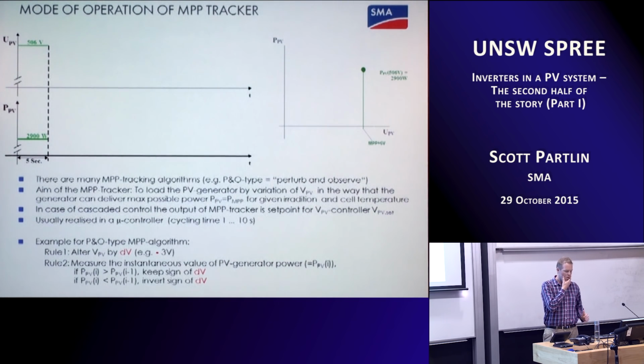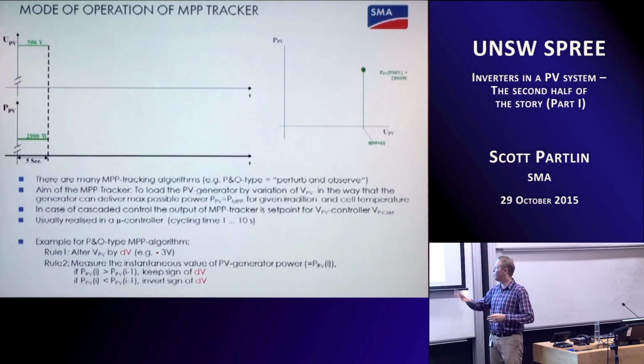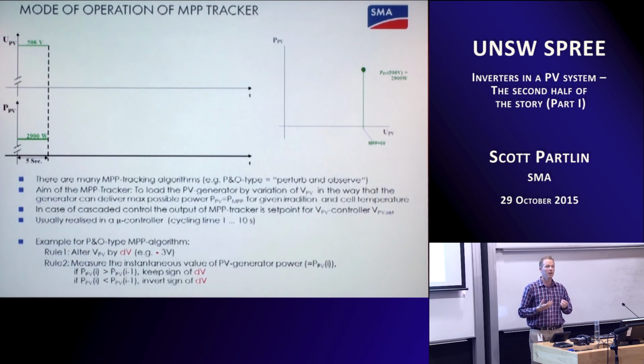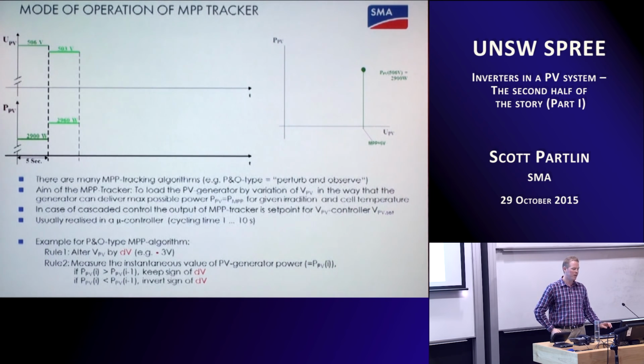So the way a maximum power point tracker within an inverter works, apologies for the tiny font, is it will initially let the PV array do whatever it wants and take that as a first reference point. Then within the inverter, it will bias the PV to play around and try to find where the maximum power point is. This illustration is meant to show what happens within an inverter very, very quickly.